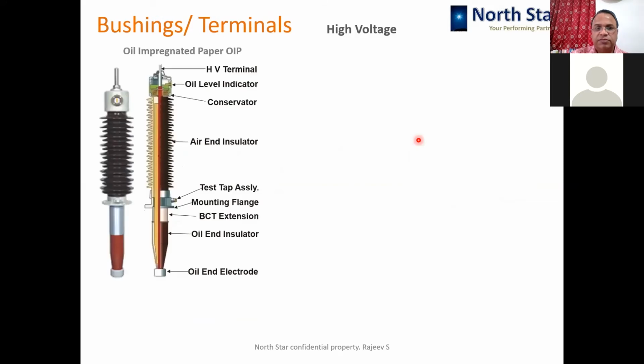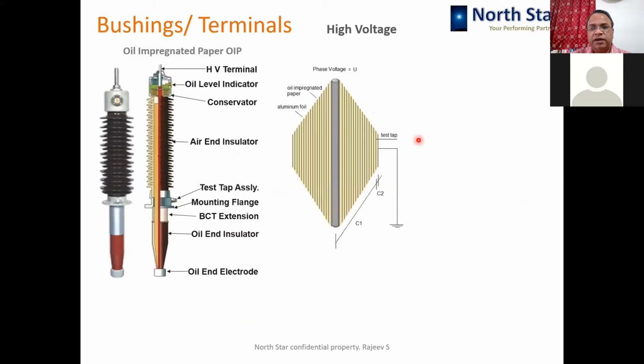On the contrary, if you look at high voltage bushings, there are two kinds of bushings now available. One is the oil impregnated paper, or OIP, bushing. These bushings typically work on the principle of capacitance, where you alternate layers of aluminum foil and insulation paper like this. So it forms the capacitance, and you get a very good operating voltage because of this capacitive design. So you get a comparatively compact bushing, capable of taking up higher voltages.